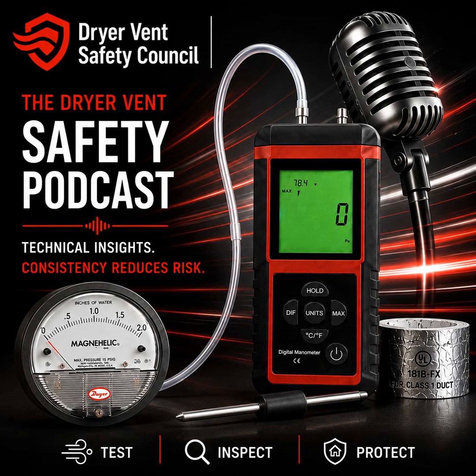Yes. The Dryer Vent Safety Council promotes a very specific 5-step sequence for this. It goes measure, inspect, diagnose, service, and then measure again. That second measurement is where the truth comes out. Yeah, there's a quote in the text from Terry Rohr, the co-founder of the council, and she crystallizes the entire philosophy perfectly. She says, the before reading tells you where the system started. The after reading tells you what the service actually accomplished. Without both, how do you really know?